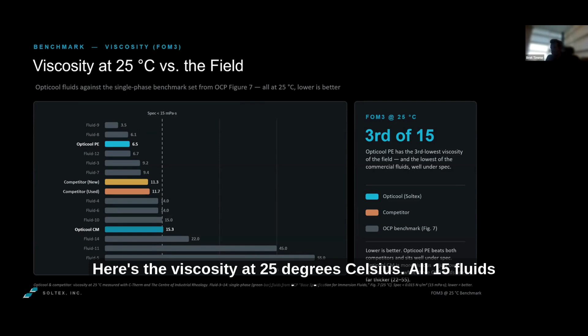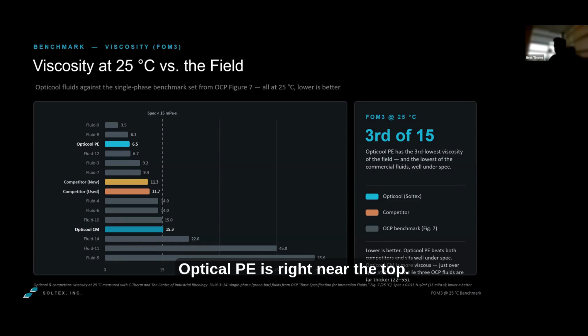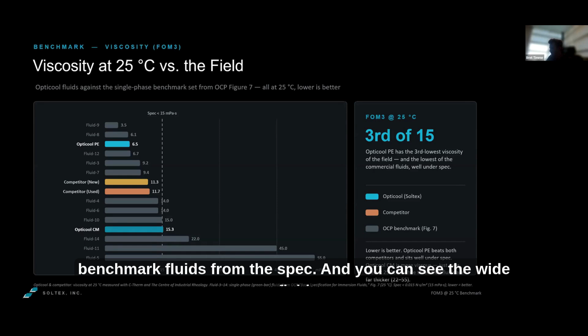Here's the viscosity at 25 degrees Celsius, all 15 fluids ranked. This time the lowest is the highest, since lower viscosity is correlated with better heat transfer. Opticool PE is right near the top, third lowest of the entire field and the lowest of any of the commercial fluids, beating both competitor samples comfortably. The two fluids ahead of it are unnamed benchmark fluids from the spec, and you can see the wide field - a few of these fluids are 3 to 5 times more viscous and will fail the spec line.